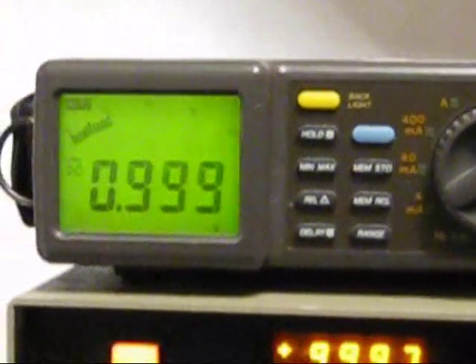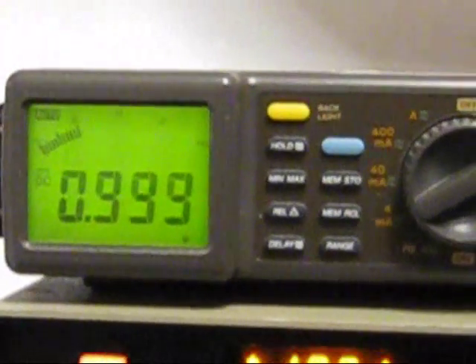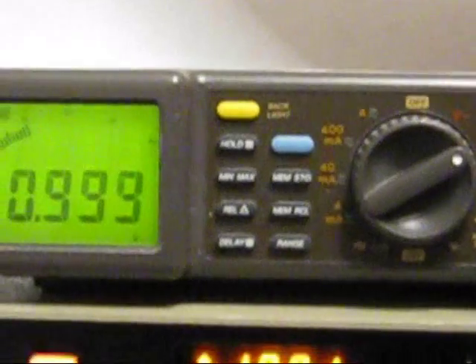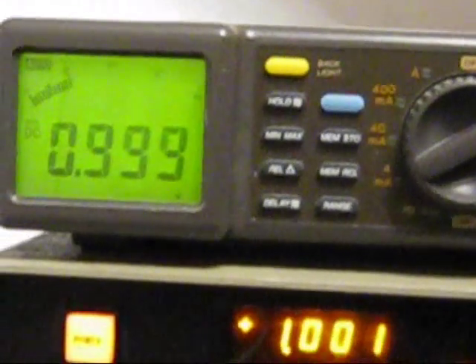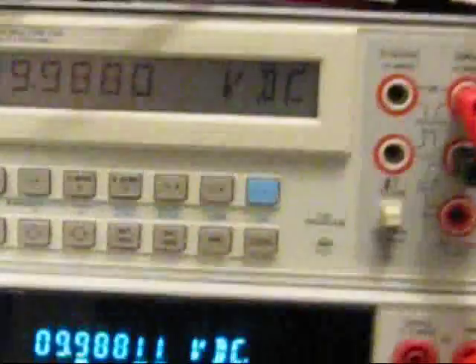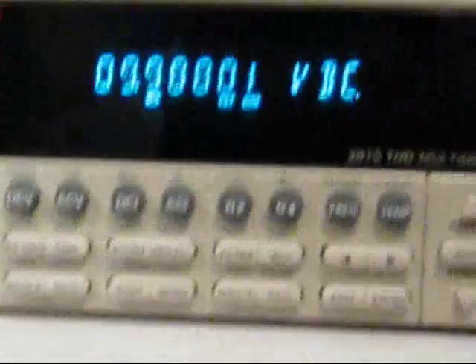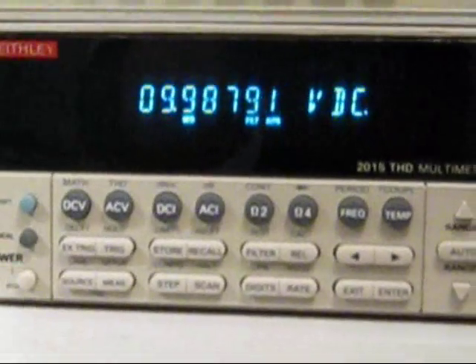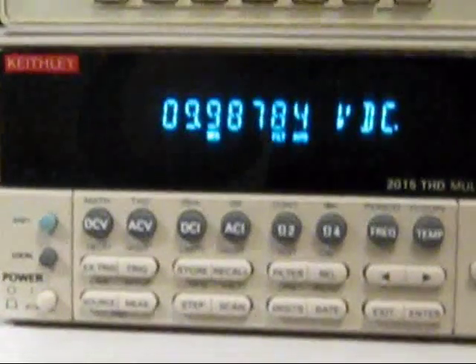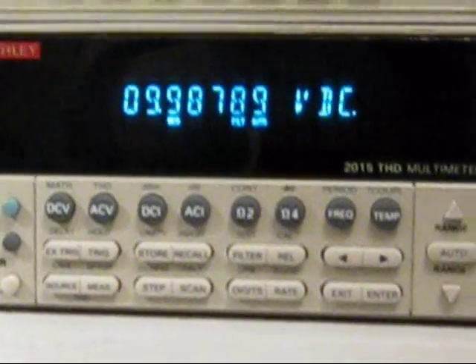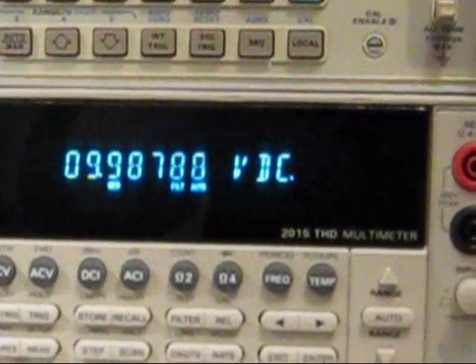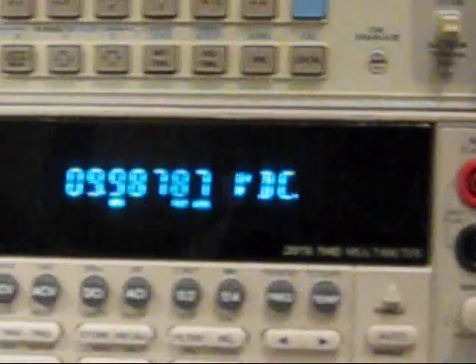Now the Datron is a manual ranging device, so let's put that on the 10 volt range and switch the calibrator up to the next range. And if we work our way up from the bottom, we have got 0.99878.